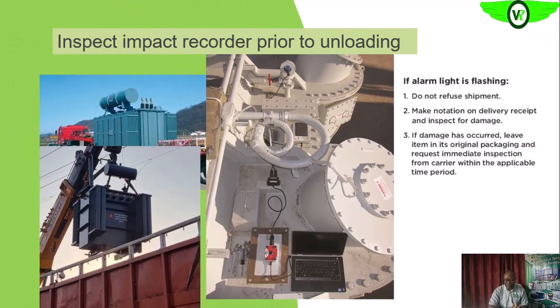If the degree of impact is within a tolerable level, of course, we can accept the transformer. Once it is flashing like that, we just make a notation on the delivery receipt and inspect the transformer for any visible signs of damage. If damage has happened that is very severe and clearly visible, then we can leave the item in its original package and request immediate inspection from the delivery company, so that the actual degree of impact will be ascertained and confirmed by everyone.